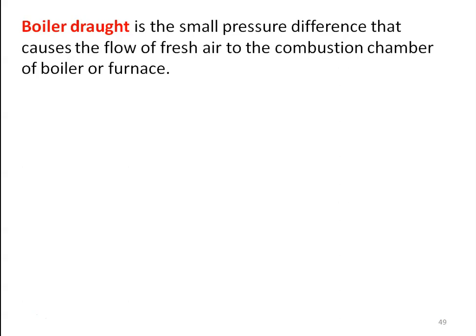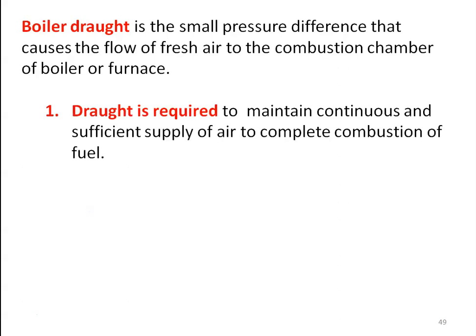Boiler draught is defined as the small pressure difference that causes the flow of fresh air to the combustion chamber of the boiler or furnace. We require air for combustion, and the air is supplied to the boiler by means of draught. The draught is created by the pressure difference between the atmospheric air and the pressure of the gases inside the combustion chamber. The draught is required to maintain continuous flow of sufficient air supply to complete combustion of the fuel.